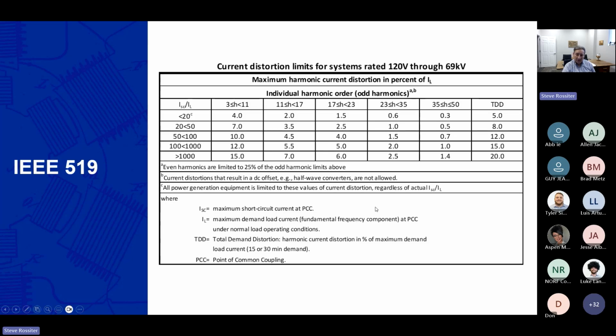But that's how IEEE 519 actually evolved nowadays to no longer a recommended practice, but a standard which all engineers would use in prudent engineering of a facility. And so therefore, either they're going to have provisions to say, okay, we need to reduce the harmonic distortion from these devices by this much, or we need to have a device that doesn't create it. Even fluorescent lights, when we changed from fluorescent lights through magnetic ballast, which were primarily a sine wave linear load, to the LED modules, which now have drivers in them, which are a little solid state device going through silicon. Even the good ones nowadays, bad ones would be in the 30, 40, 50, 70% current distortion range.